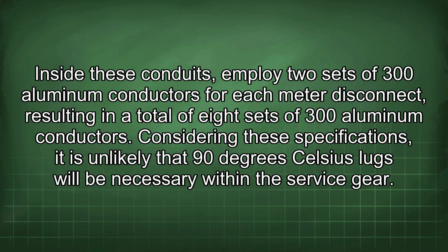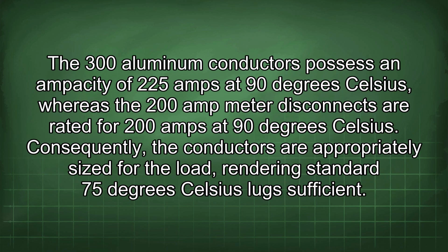Considering these specifications, it is unlikely that 90 degrees Celsius lugs will be necessary within the service gear. The 300 aluminum conductors possess an ampacity of 225 amps at 90 degrees Celsius, whereas the 200 amp meter disconnects are rated for 200 amps at 90 degrees Celsius. Consequently, the conductors are appropriately sized for the load, rendering standard 75 degrees Celsius lugs sufficient.